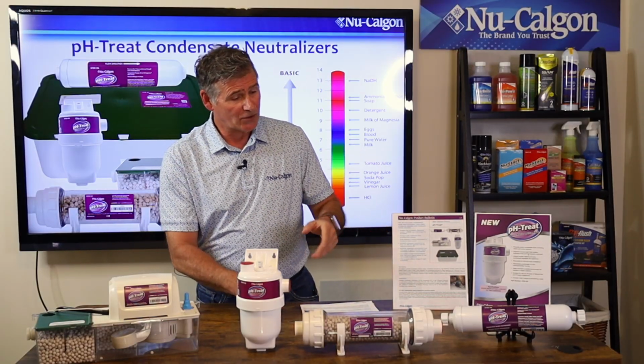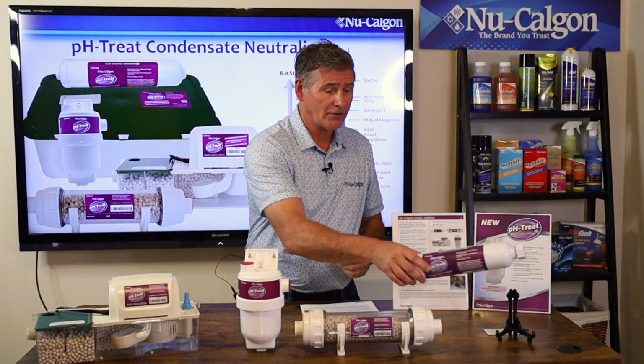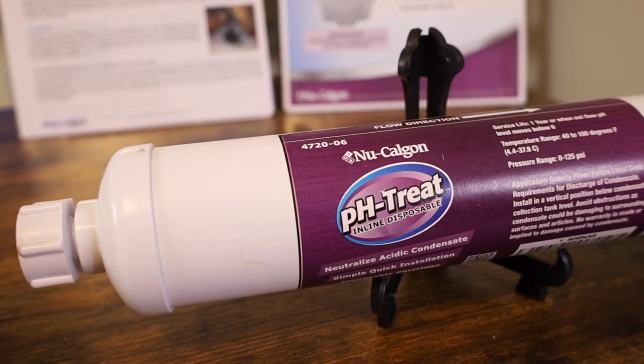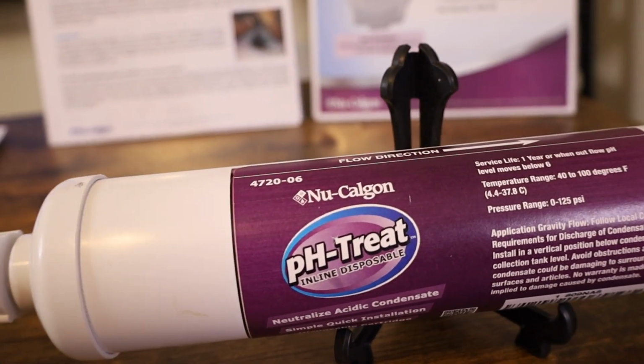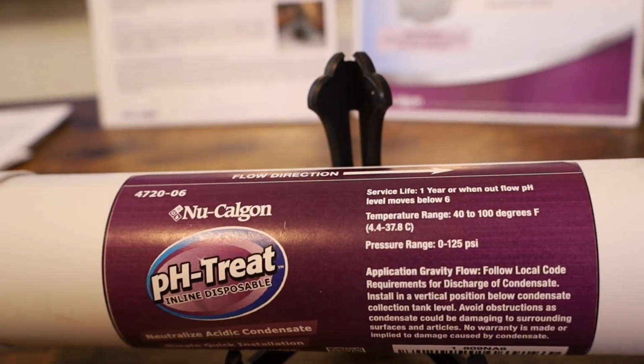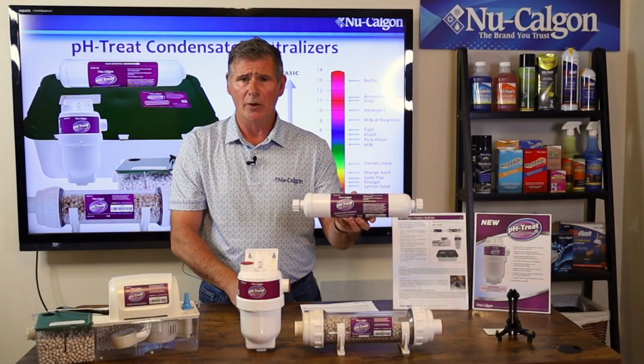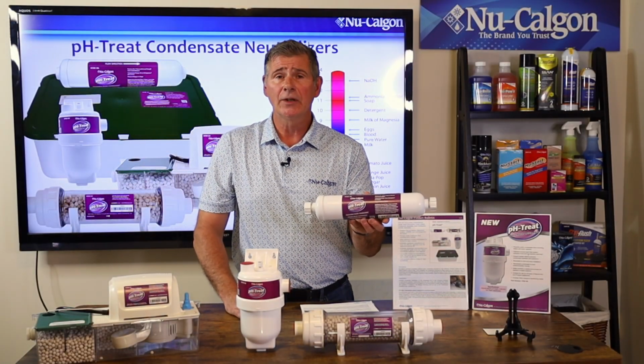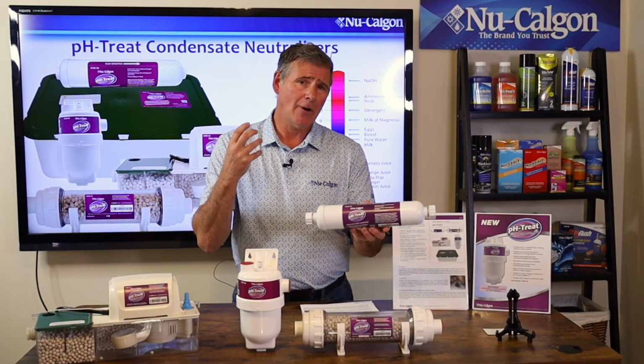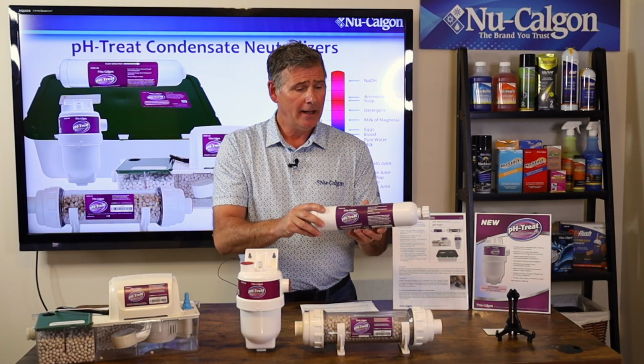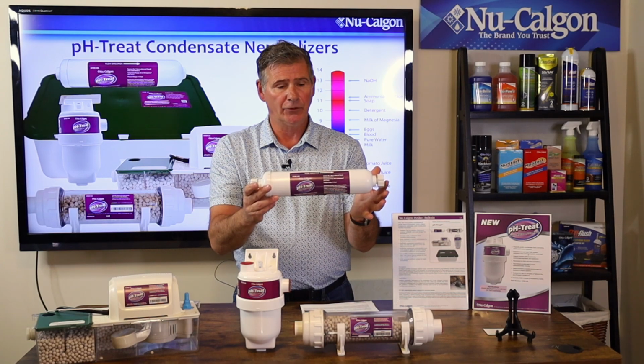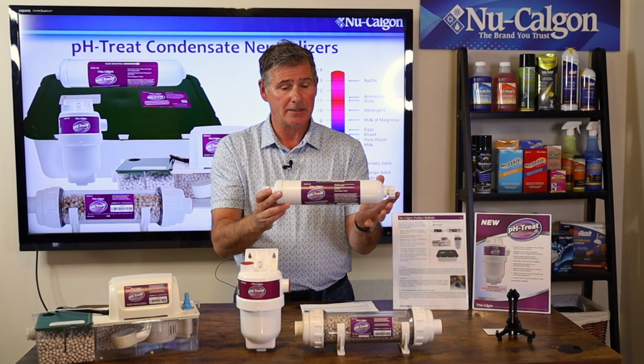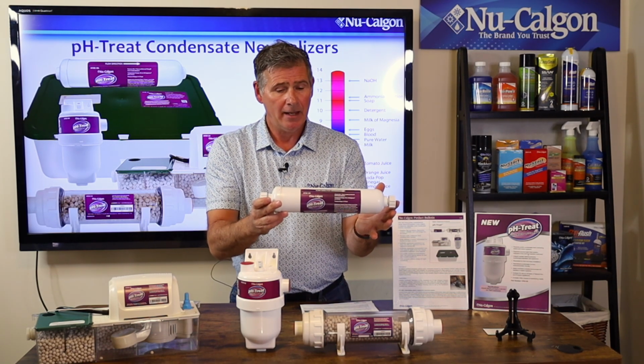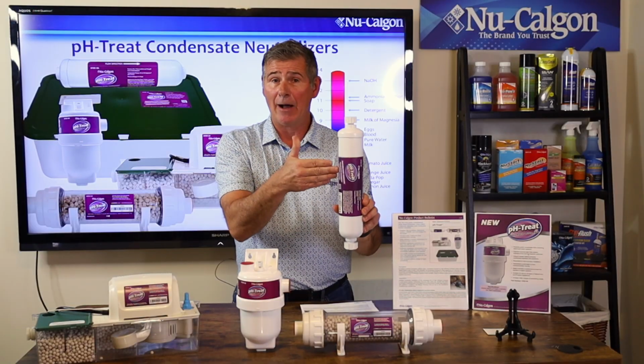So first and foremost, let's talk about the small one that we have down here. This is the smallest one that NuCalgon offers in the pH Treat lineup. This is going to do those high efficiency systems that are up to about 225,000 BTUs, or around 1 gallon per hour worth of condensate flow. This looks very much like just a water filter, and that's kind of what it is, but it's completely disposable. So this is a vertical mount version of that.